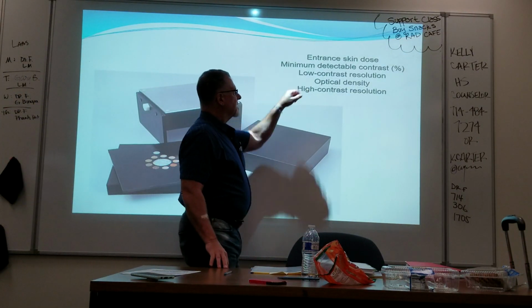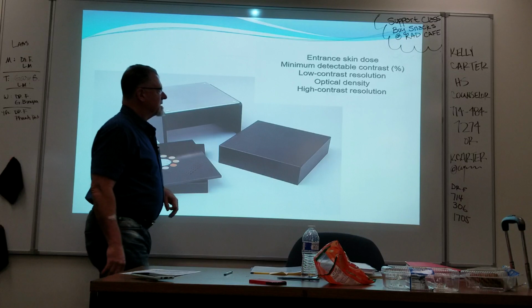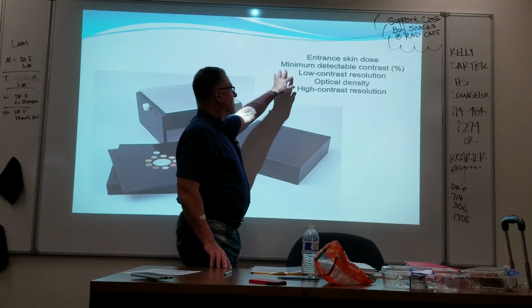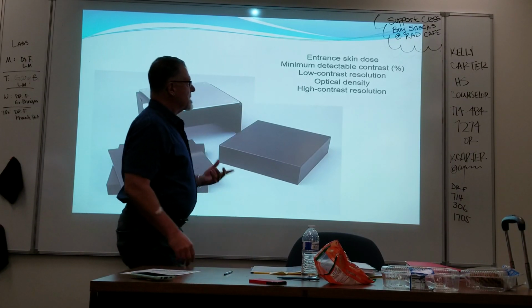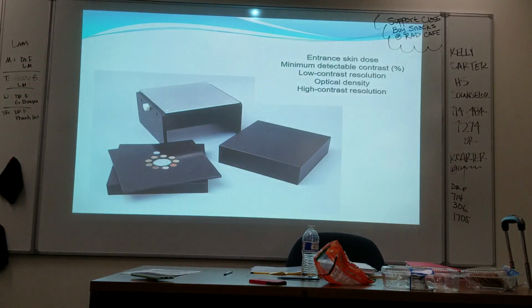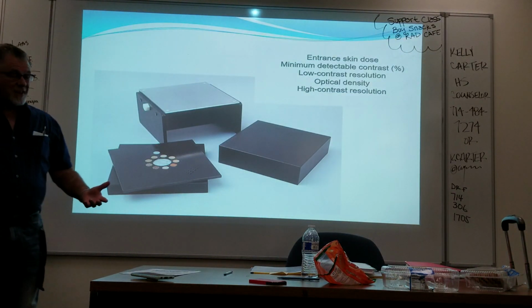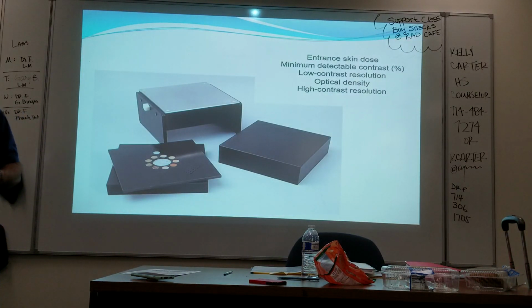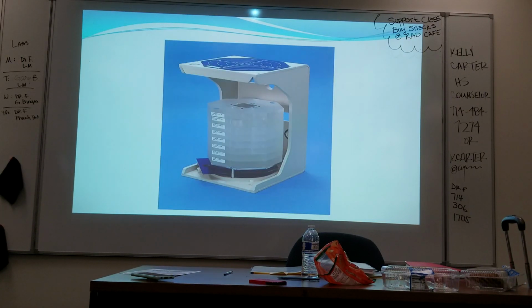differing contrast. You can figure out what the minimum detectable contrast is. That's important. If the minimum detectable contrast on a system is poor, then for studies that you need the ability to see low contrast structures, that system's not a good one to use. Phantoms can run very, very expensive.